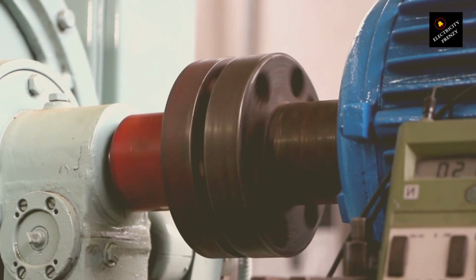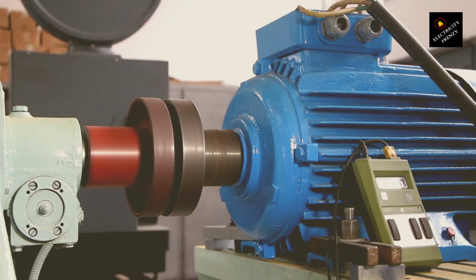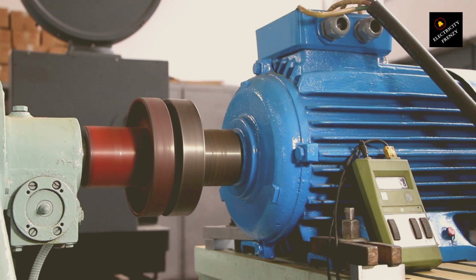At 110 volts, or lower voltage operation, the windings are connected in parallel. This effectively halves the voltage across each winding, since they share the total voltage, and allows the motor to operate efficiently at a lower voltage level.